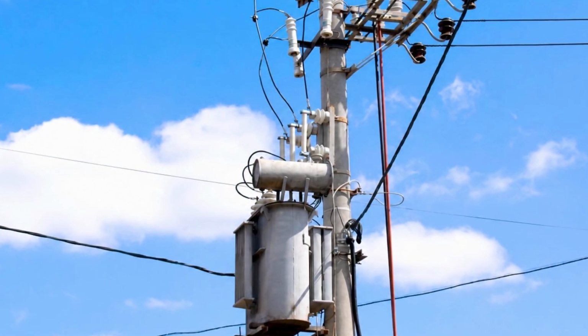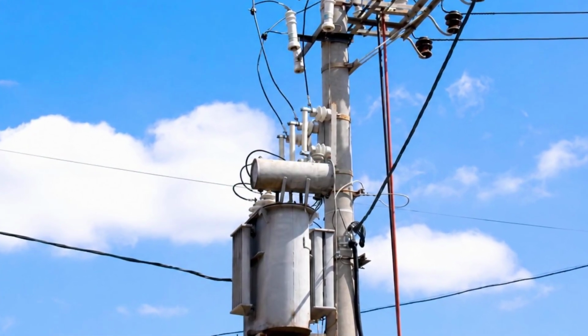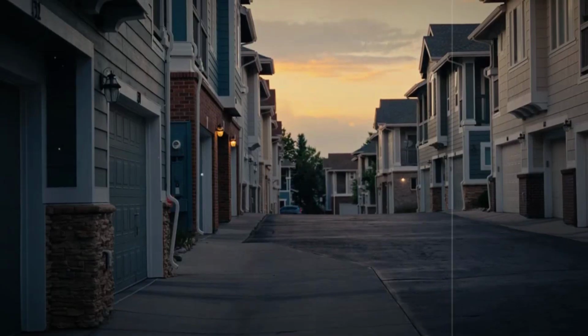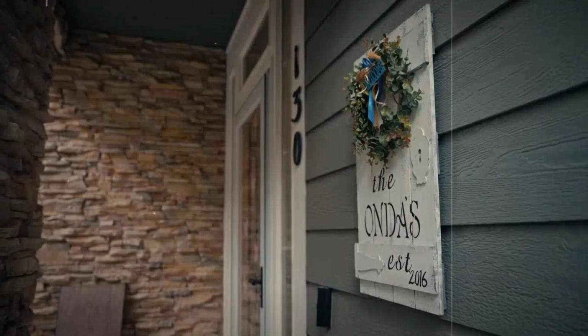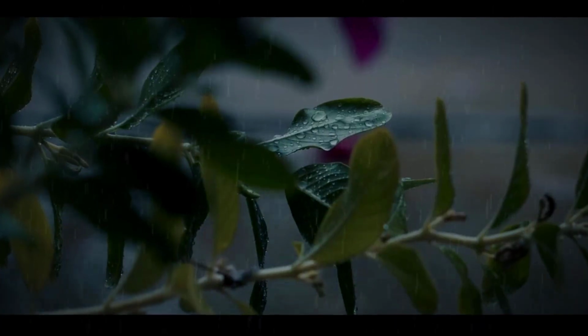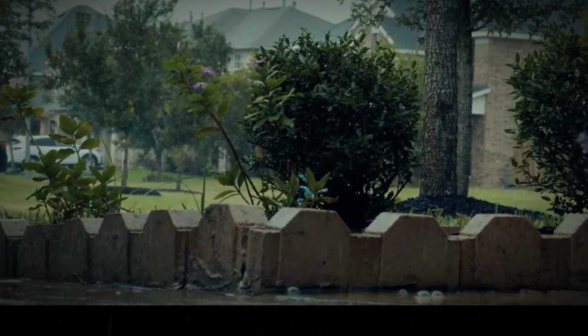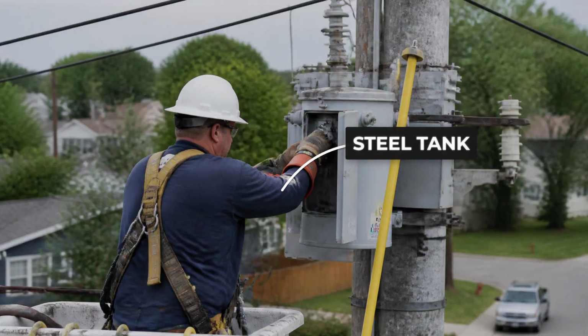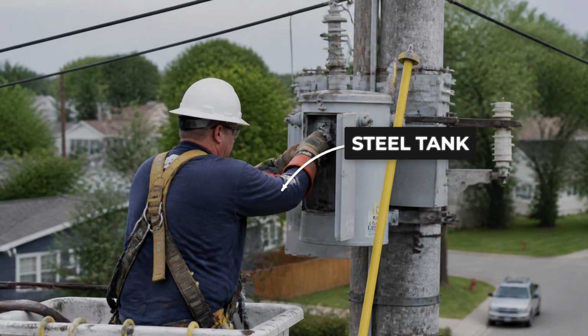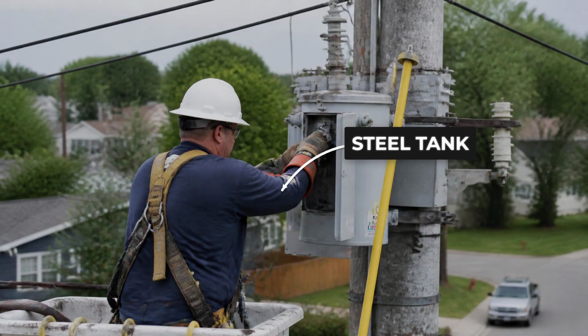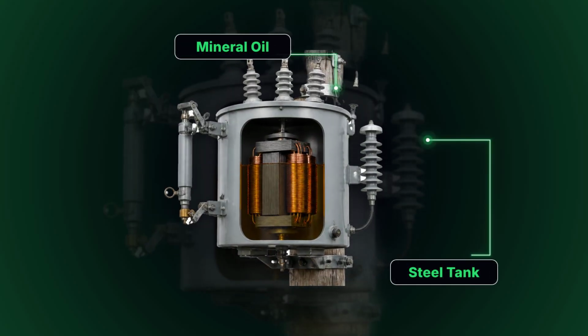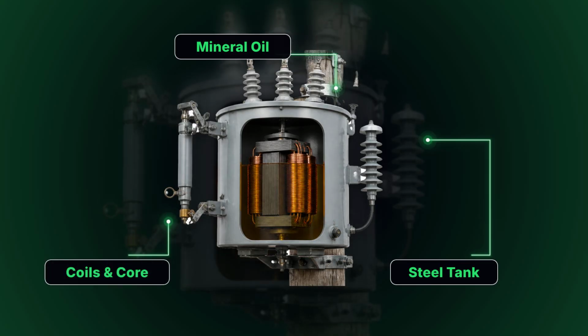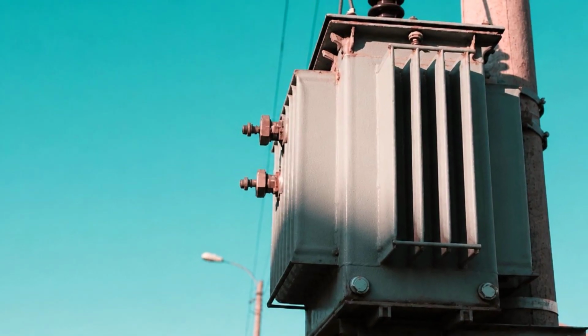These steel tanks endure decades of relentless exposure to the elements. Day and night, through freezing winters, baking summer heat waves, torrential rains, and high winds, the sealed outer shell isolates the sensitive core and windings from the outside world. Inside, the highly refined mineral oil works constantly, absorbing heat from the active coils and transferring it to the tank walls, where ambient air carries it away.